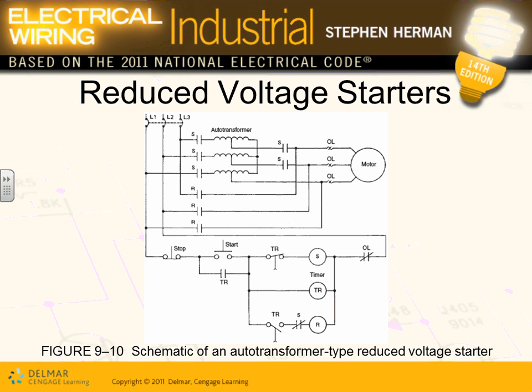Absolutely. Here's how it goes, Aaron. Your full voltage is 480, right? For 10 seconds, it dumps down through the transformer to 240. The motor starts. The torque is low, so I don't bust the machines when I give a big push to the machines, number one. And I don't dim the light when I start. That's the advantage of reducing the voltage. For 10 seconds, my motor slowly, gently starts. And you know what they do after that? They raise the voltage back to the regular voltage so the motor can give you the full horsepower and the full torque.